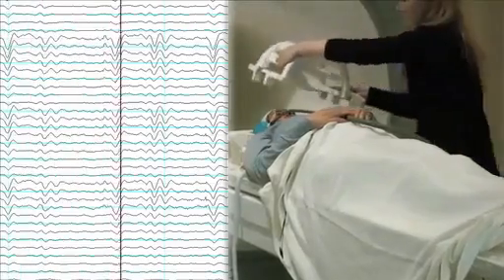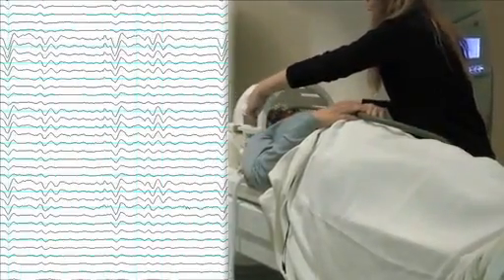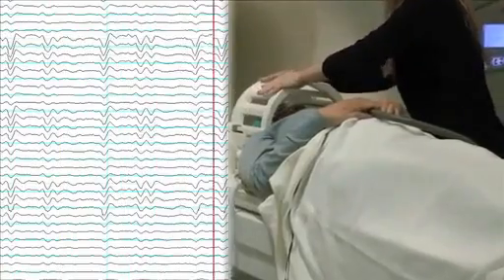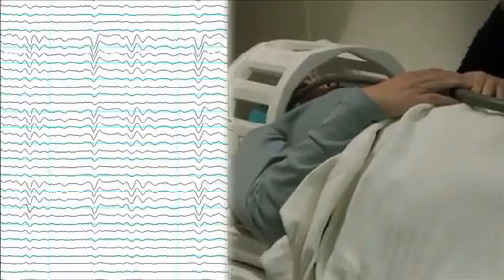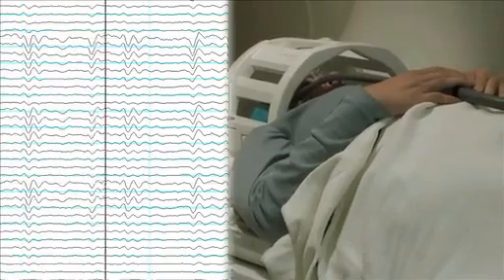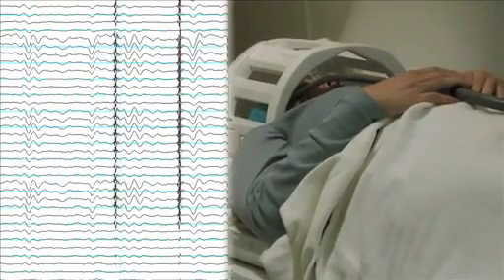The simultaneous collection of EEG and fMRI is particularly difficult because each of the devices creates artifacts in the other. The MRI effects on EEG are especially challenging, as the RF portion of the imaging system utilizes signals of up to several hundred volts, while the gradients impose time-varying magnetic fields at upwards of 45 tesla per second.